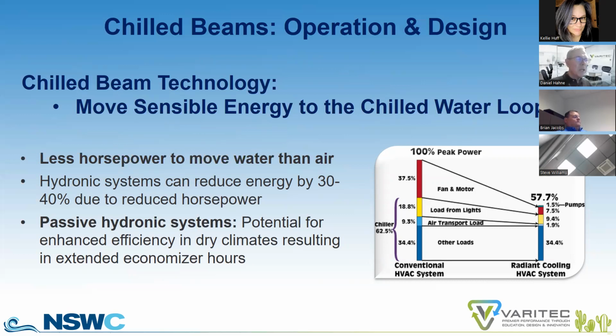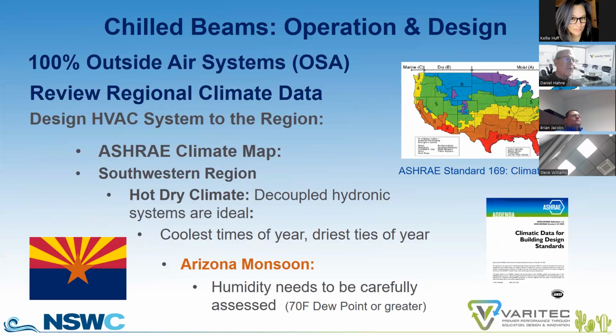To maximize that potential, you have to have a sound design strategy, of course, and it also depends on the geographic region of the building. Is it in the southeast where there's high humidity, or is it in Phoenix, Arizona, where we have mostly a dry condition throughout the year? Passive chill beam systems offer another level of potential energy savings because they use displacement ventilation as the air delivery solution of choice, which uses a higher entering air temperature, so you can double your economizer hours here in Phoenix, Arizona during our more temperate, drier times of the year. Again, you need to be aware of the geographical location.